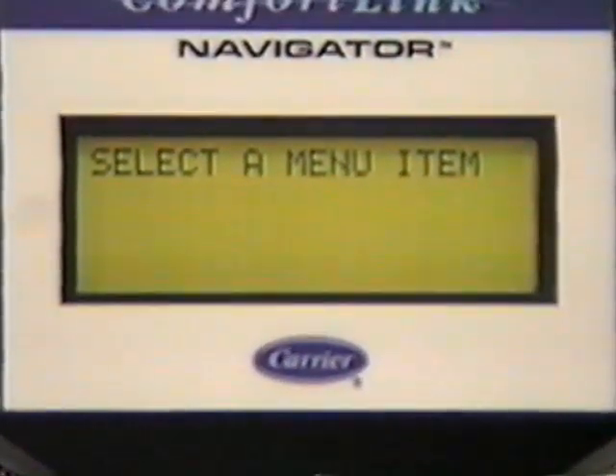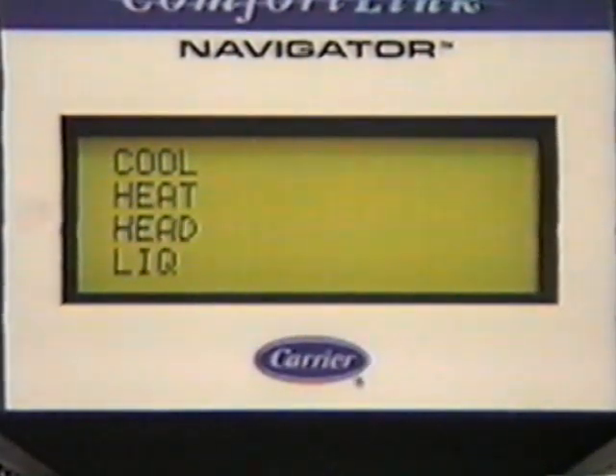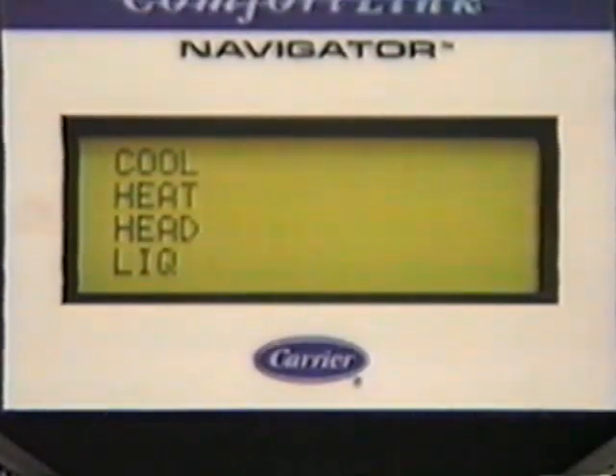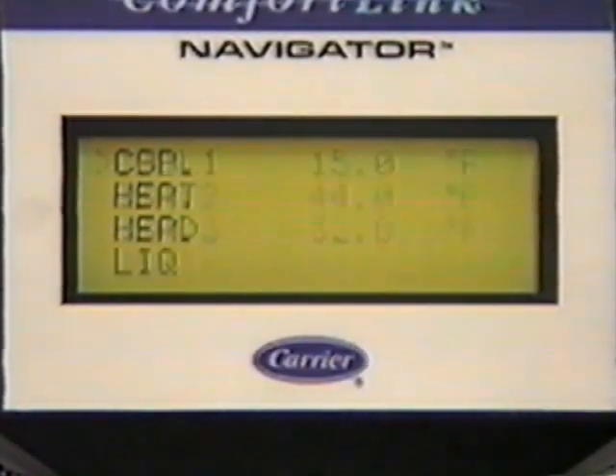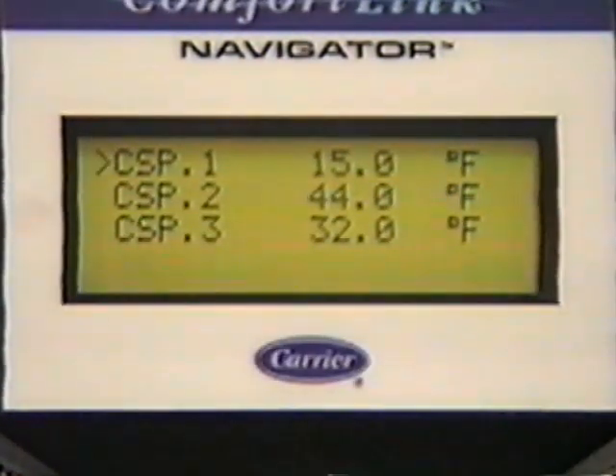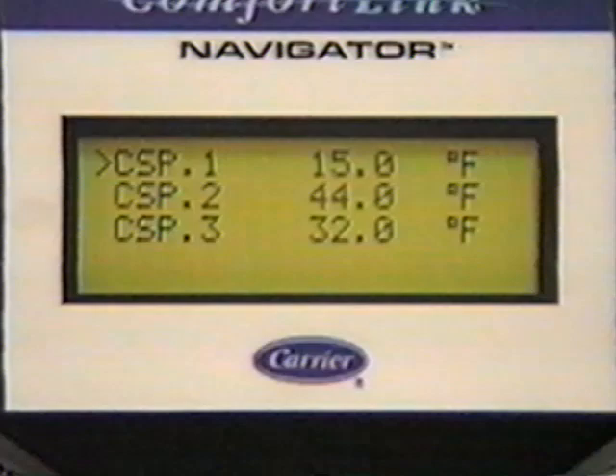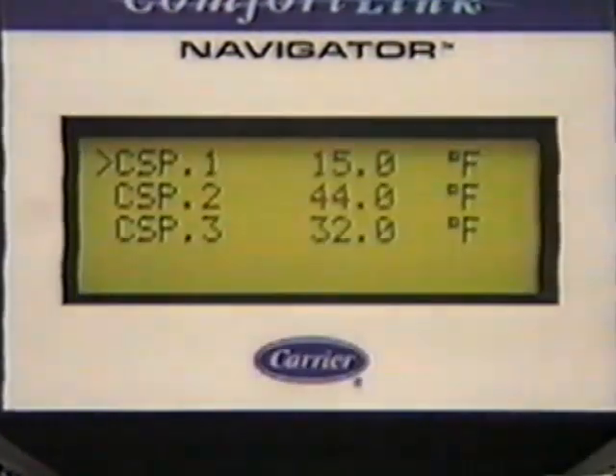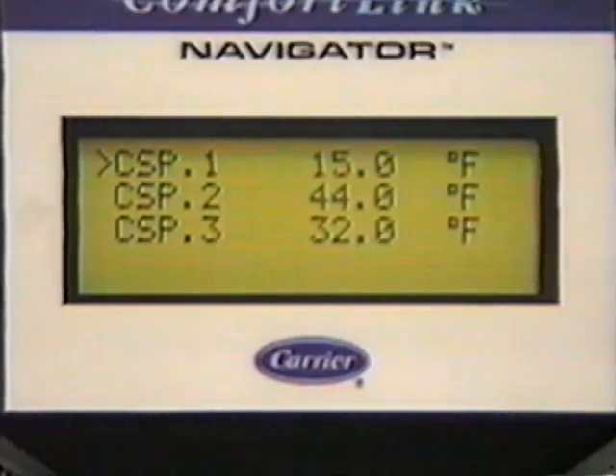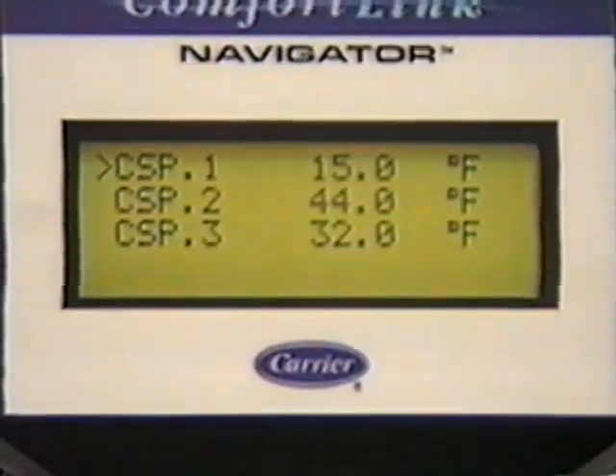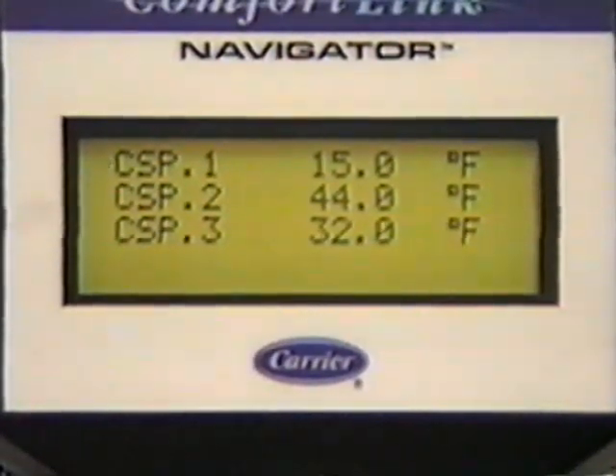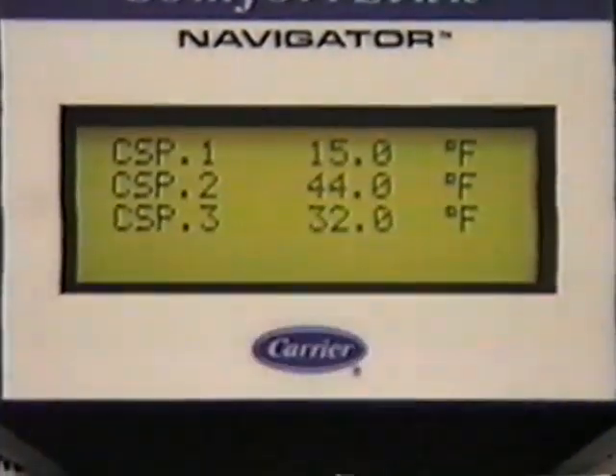Okay, the next menu item is set points. You'll see cool, heat, head, liquid. Probably the only one you really want to enter on would be cool. So just hit enter. You'll see there's a number of different set points. Because we're only doing one mode, and that's just making ice, we only utilize the first set point. So the other set points are meaningless. They could be anything, because we haven't configured the microprocessor to utilize those in any way. So you're just using the one set point, and that's cooling set point 1, and again that's 15 degrees. If you wanted to change it, on any item you can hit enter.